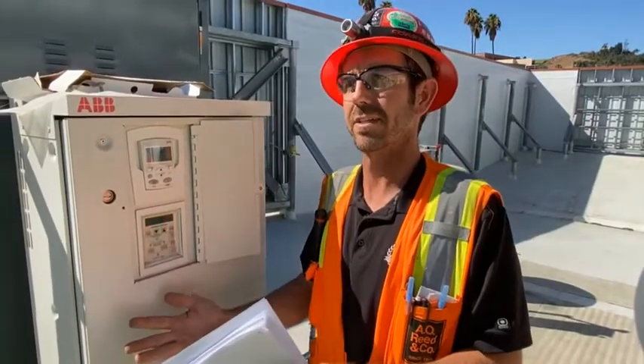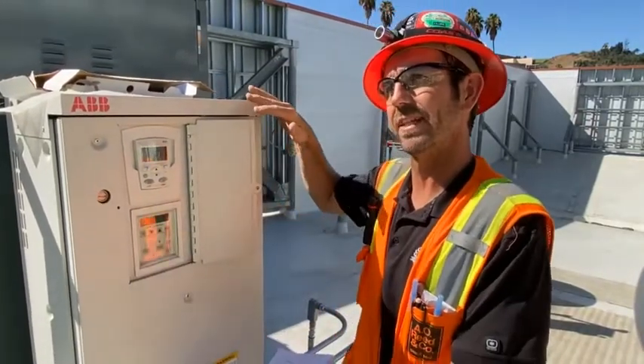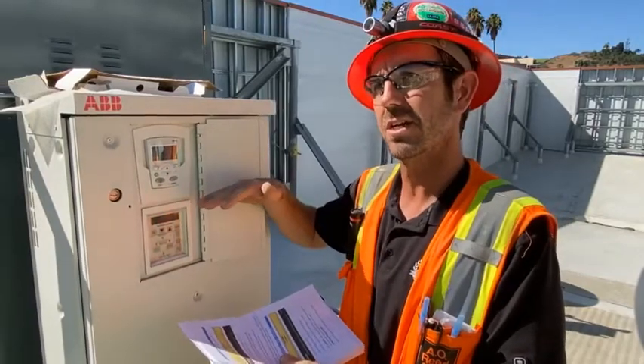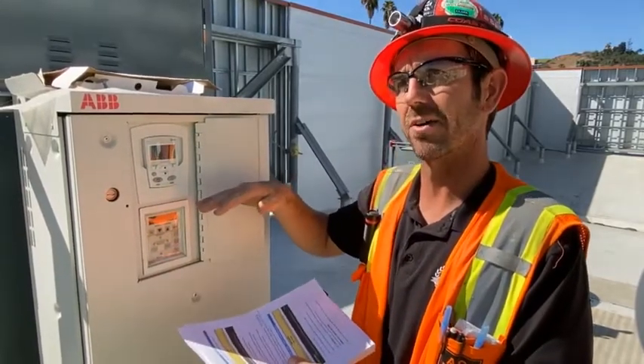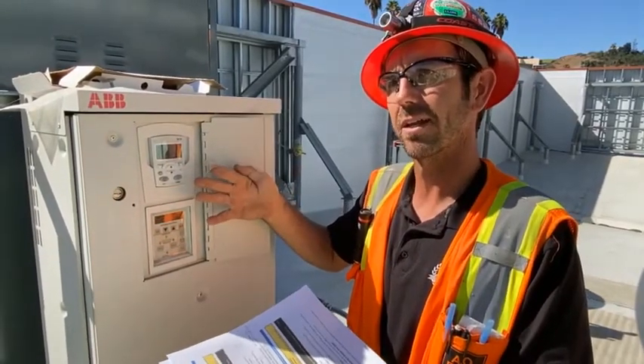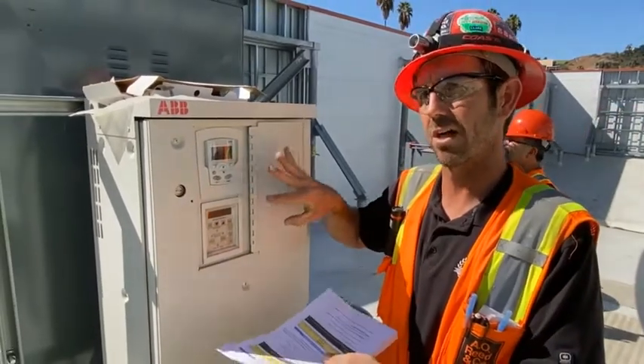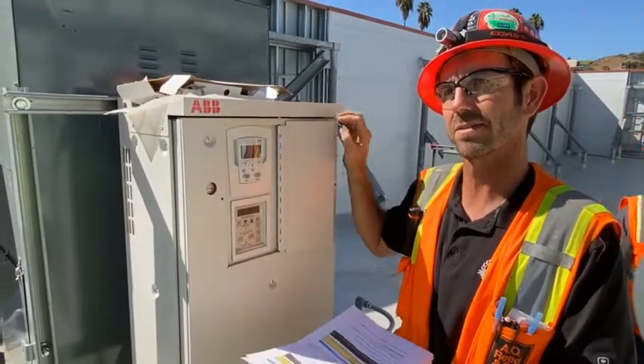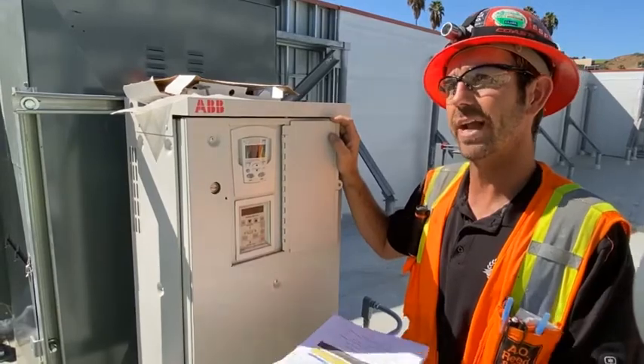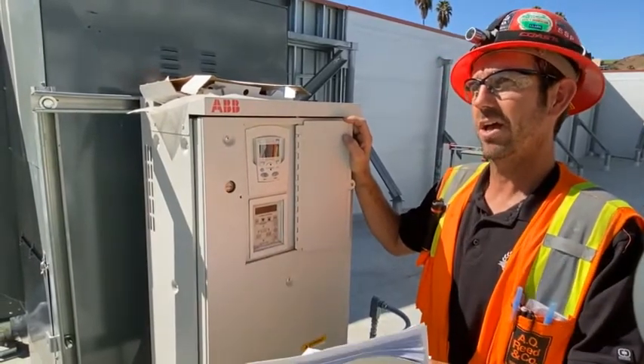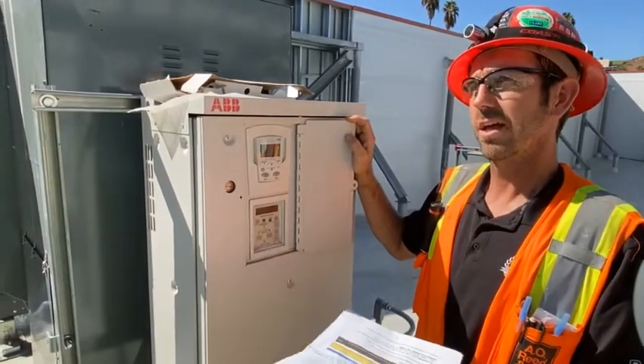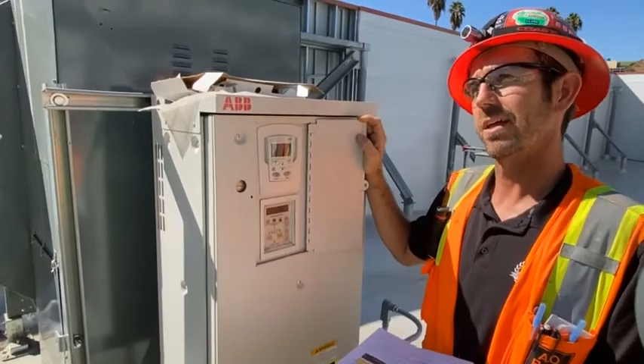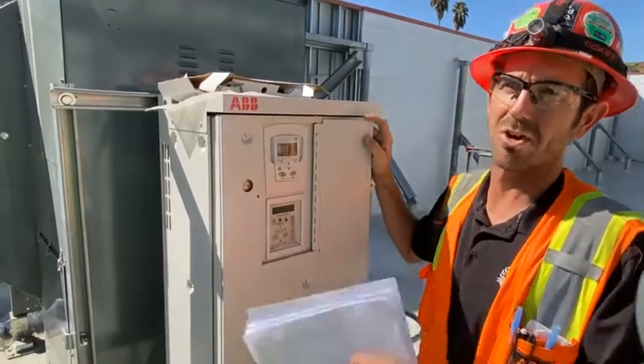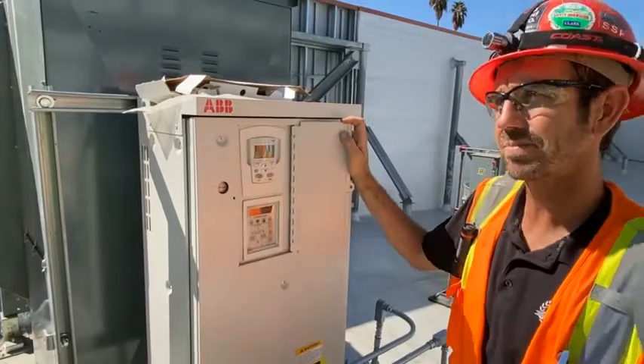Right. If we don't need it at 60 hertz, having this VFD, they knew the airflow might need to change. We can change that airflow depending on the CFM we need. But it's not a modulating system. It's locked in at 43 hertz per the balance. Does that make sense? Yeah, I know what you're saying, but it's a little bit overkill, because if you're going to run it at a certain speed, you're saving energy by running the drive at a lower speed. They could have just balanced it.